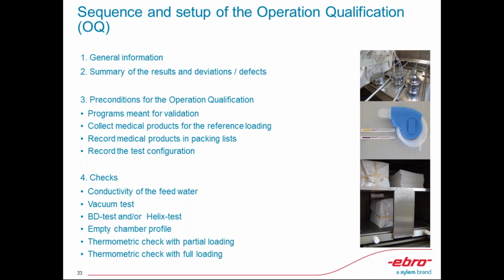So we have here the sequence with the OQ. I'd like to go immediately to number 4, the checks: the conductivity of feed water, vacuum test, BD, the Bowie and Dick test or helix test, empty chamber profile, thermometric check with partial loading, thermometric check with full loading, and sometimes even the thermometric check for empty chambers. I went to number 4 immediately because this is where Ebro can really help the CSSD units. We will go to the BD test or the Bowie and Dick test in detail later.